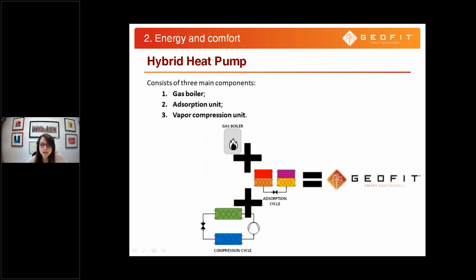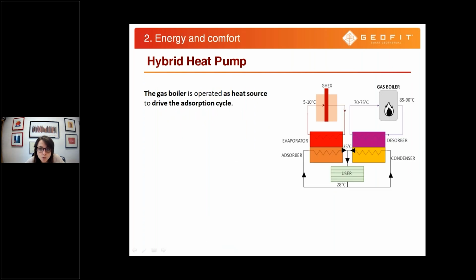The second element we had to design was the hybrid heat pump, which used a gas boiler to start the production of heat. Our heat pump is composed of three elements: the gas boiler, the adsorption-desorption unit, and the vapor compression unit. Essentially we use the gas boiler as a heat source to drive the adsorption cycle, so it's a heat pump that uses thermochemical energy storage to work.